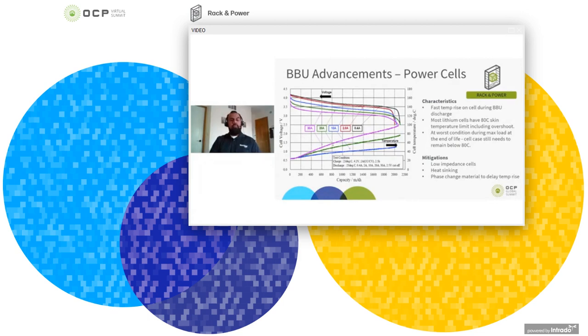One of the critical design elements for BBUs is finding cells that can provide high power. This is an example of a discharge curve for a very high rate 18650 NCA cell. It can provide up to 30 amps continuously for the duration. And as you can see in the graph, the temperature rises very quickly. So we need to find cells that are very low impedance so they don't generate a lot of self-heating.